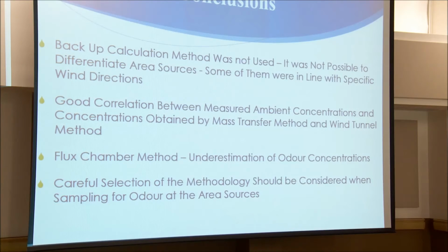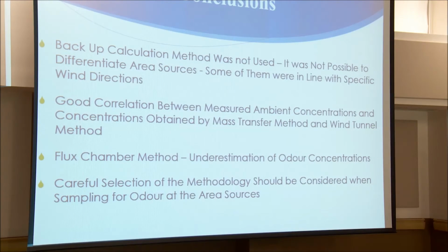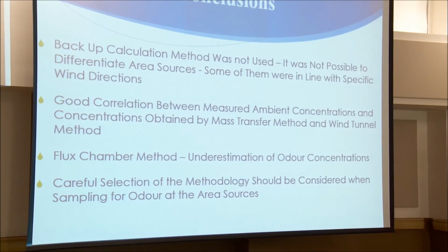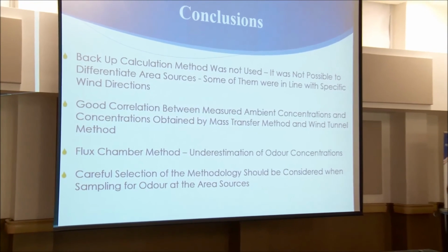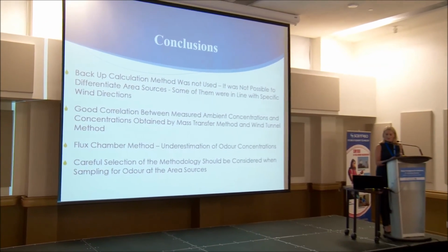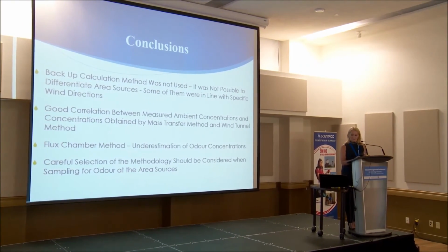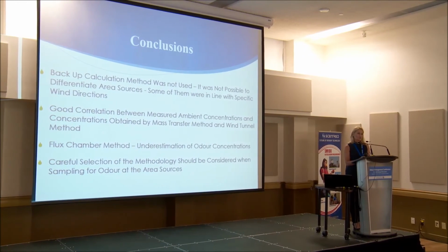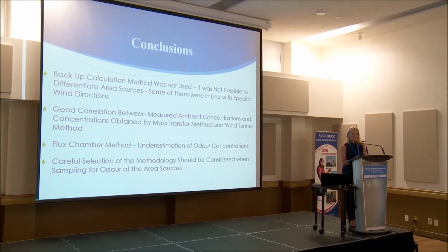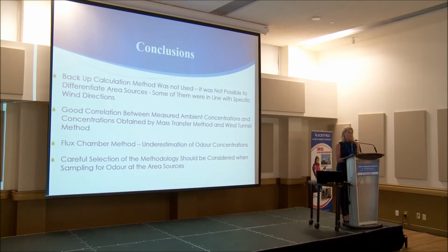Flux chamber method underestimates the odor concentration. Therefore, when assessing the odors from a wastewater treatment plant or any surface areas, we should really consider which methodology we'll be using, and it's very important, especially when the complaints occurs.